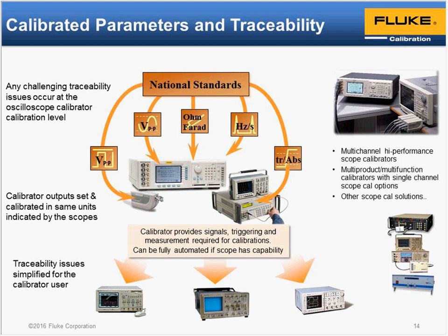To calibrate the oscilloscope using those standards for parameters directly would be quite a difficult task. By providing all of the functionality in the calibrator and calibrating the calibrator, the user of the calibrator doesn't have to do that calibration themselves. They can, if they wish, support the calibrators themselves, or they can use the services that the manufacturers, ourselves and other manufacturers, would provide. The users then avoid having to go through all of the complex procedures and metrology, which in many cases, certainly in terms of the peak-to-peak voltage and rise time, is quite difficult.